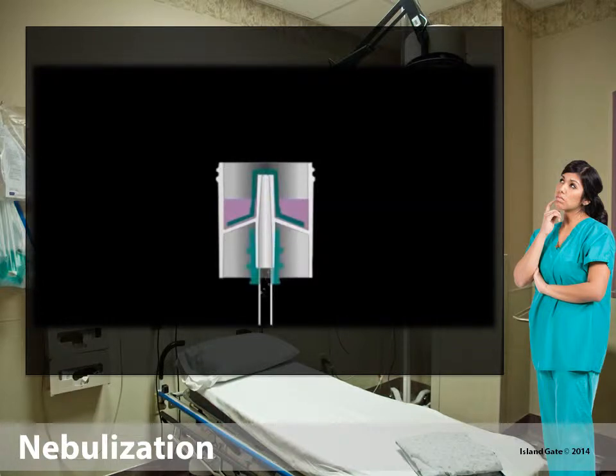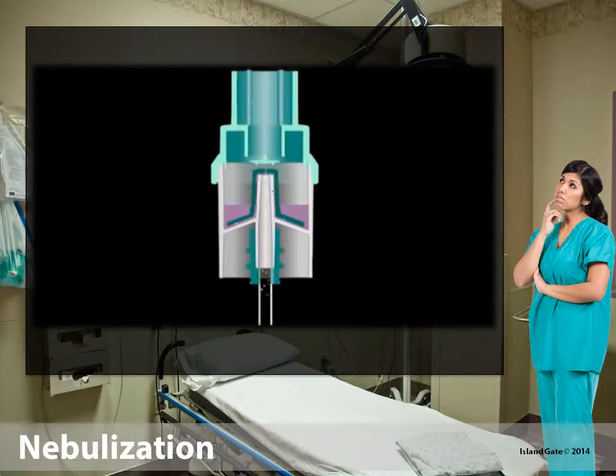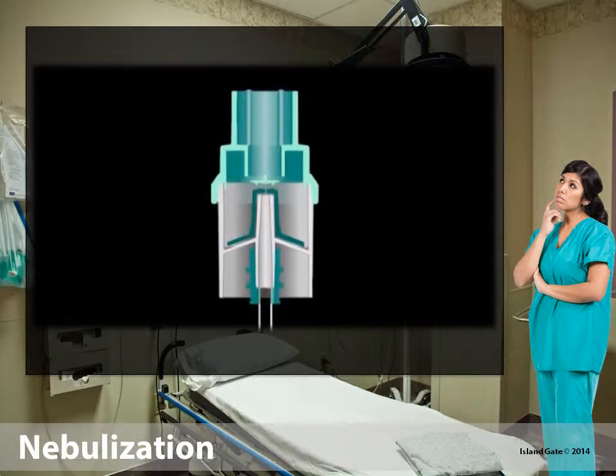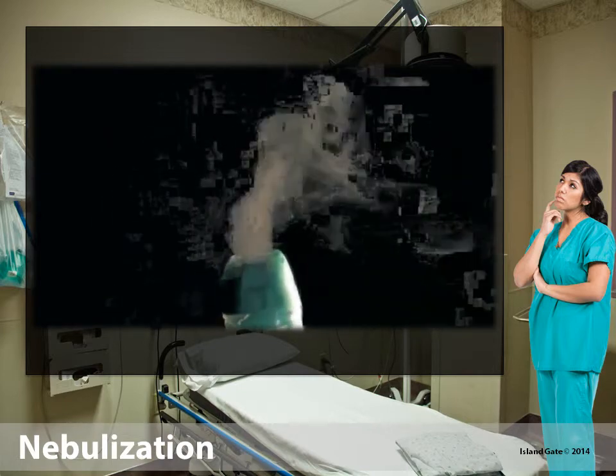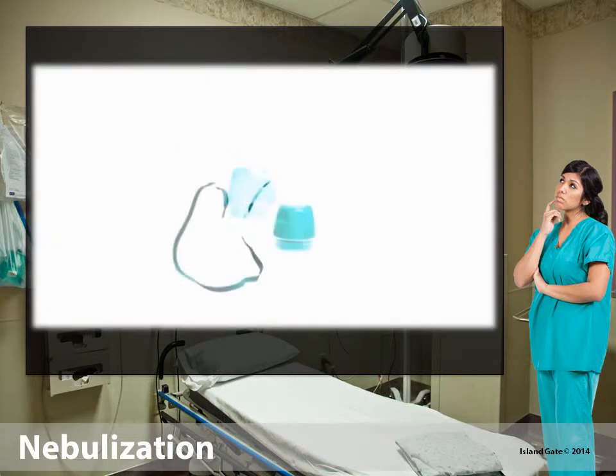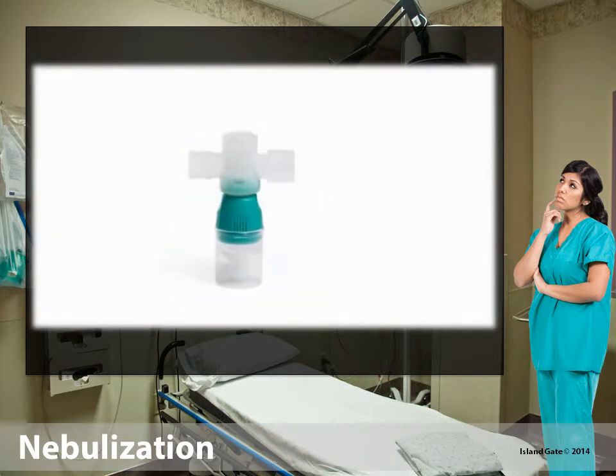The flow of gas is driven up a tube through the center of the chamber, creating an area of low pressure, which draws the drug up to the top of the chamber itself. The aerosol produced is then forced at very high speed against the baffle, which recycles the large particles. The mist of appropriately sized particles of the drug then flows out of the chamber. The delivery system can be either a mouthpiece, a face mask, or a T-piece.